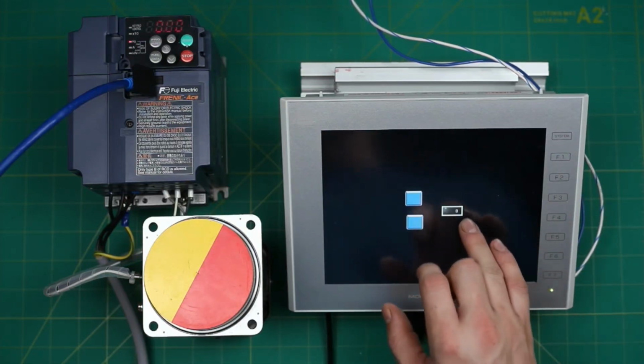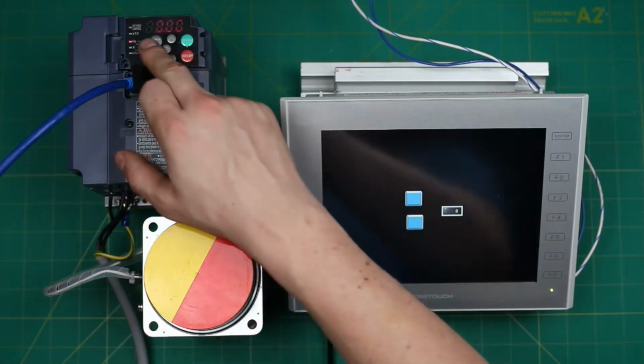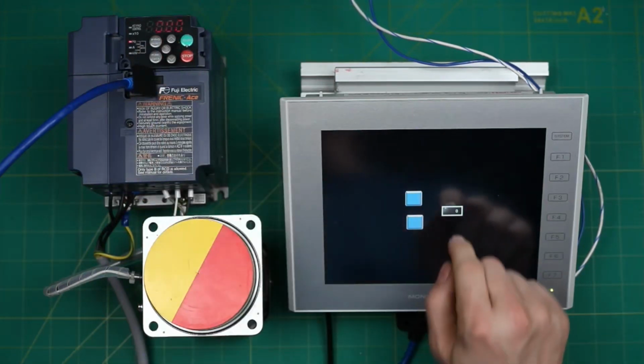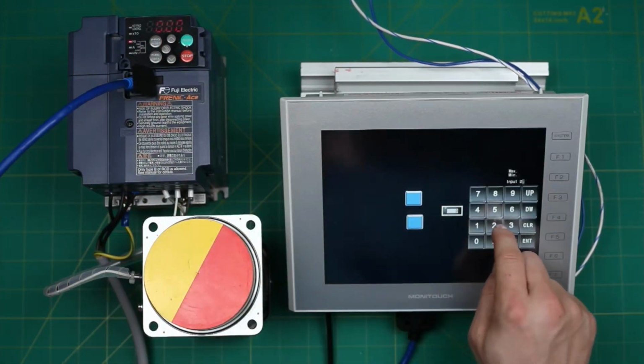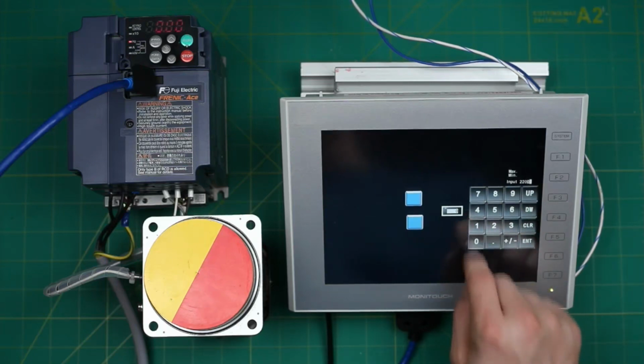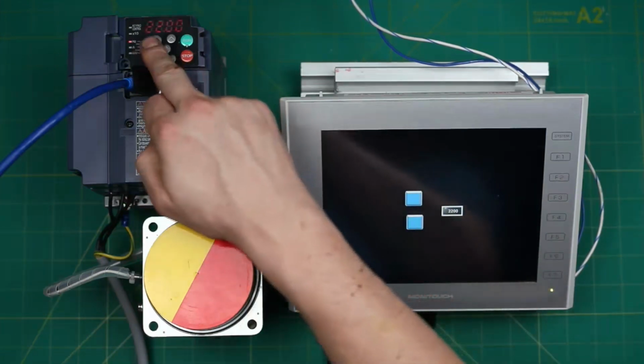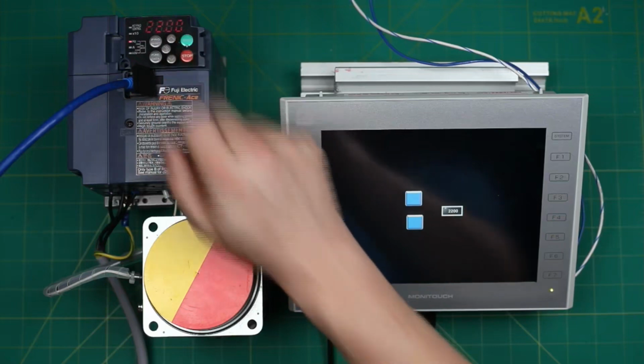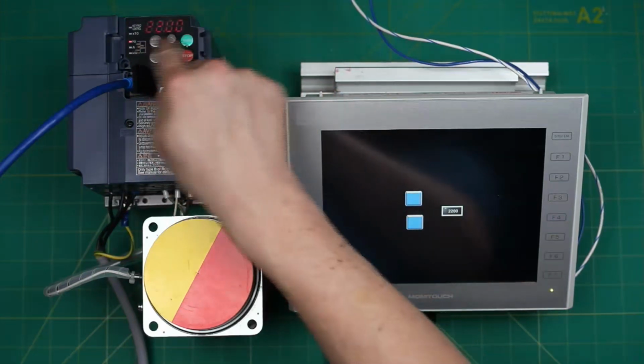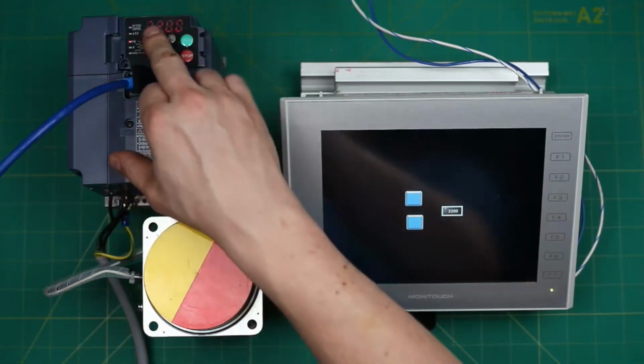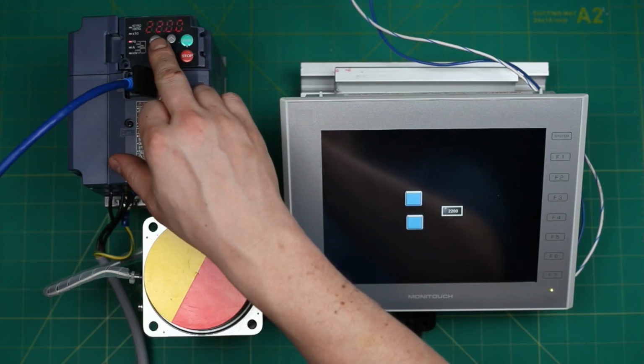As you can see, there is a 0 on the HMI and a 0 on the VFD. If we click here, we hit 2200, enter. We now see 2200 over on the VFD. This is a frequency reference of 2200.